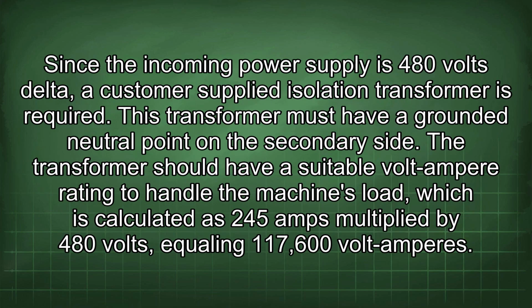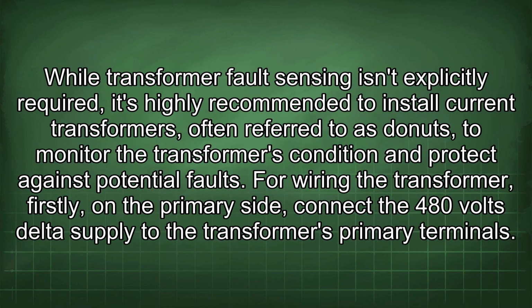Since the incoming power supply is 480 volts delta, a customer-supplied isolation transformer is required. This transformer must have a grounded neutral point on the secondary side. The transformer should have a suitable volt-ampere rating to handle the machine's load, which is calculated as 245 amps multiplied by 480 volts, equaling 117,600 volt-amperes. While transformer fault sensing isn't explicitly required, it's highly recommended to install current transformers, often referred to as donuts, to monitor the transformer's condition and protect against potential faults.